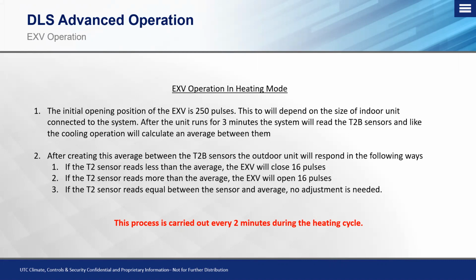That's right at that sweet spot. There's no need to adjust. And just like the cooling mode, this process is carried out every 2 minutes during that heating cycle. Okay, again, so we have to think how the refrigerant flows. So we know that the reversing valve is shifted. We're sending hot gas to the indoor unit. We're sending liquid back to the outdoor. Okay, and that's where EXV is.